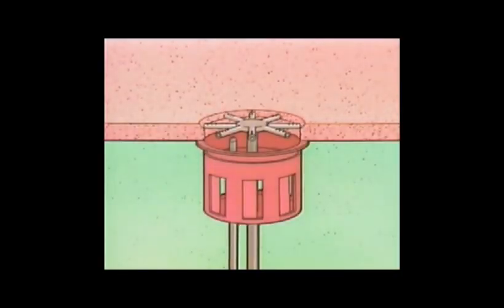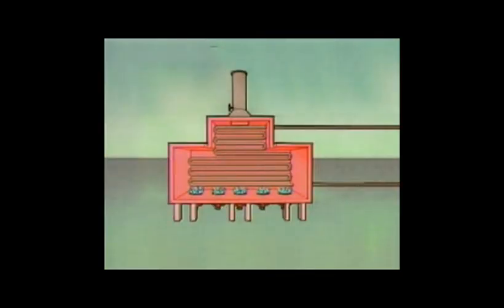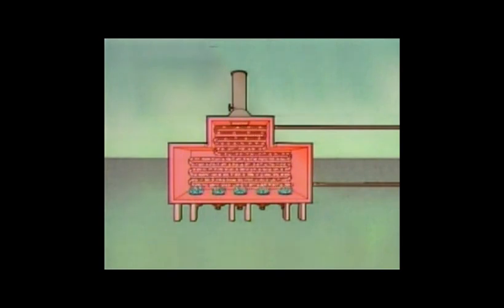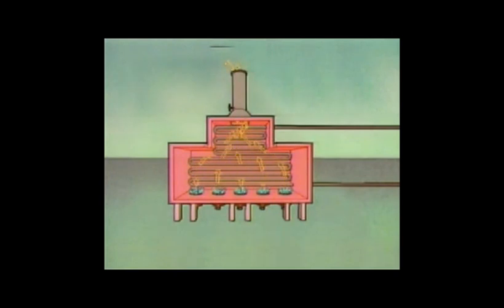All parts and systems associated with the furnace accomplish one basic task: heating a process fluid. Furnace operation can be broken down into three basic actions. First, air and fuel are introduced into the furnace, mixed by the burners, and ignited — as the fuel burns, a chemical reaction produces heat. Second, the heat is transferred to the process fluid flowing through the tubes by conduction, convection, and radiation. Third, the combustion gases produced by burning fuel rise through the stack and are exhausted to the atmosphere.